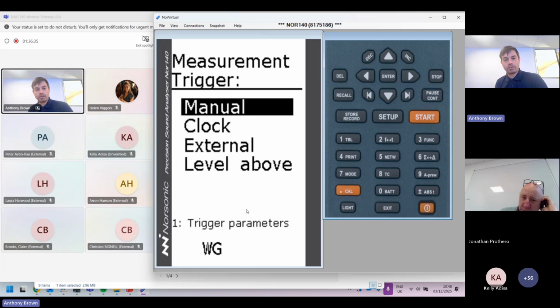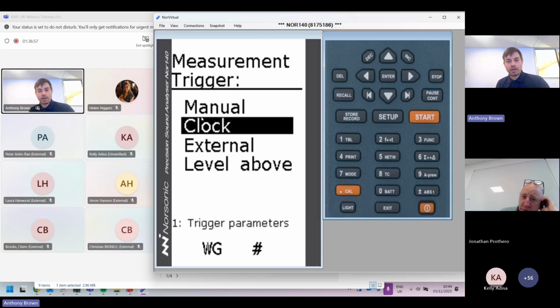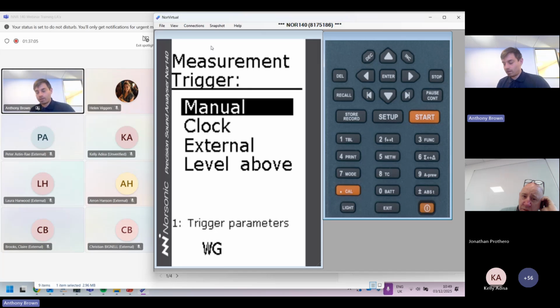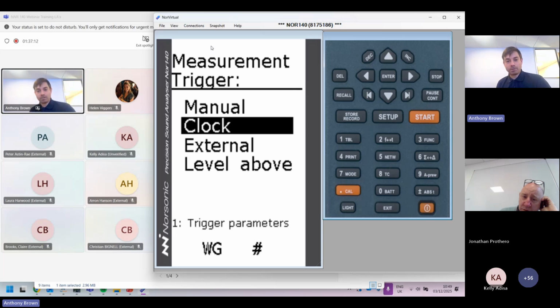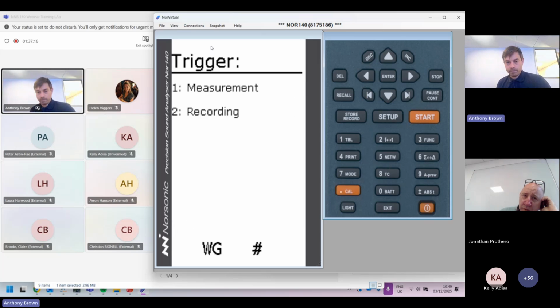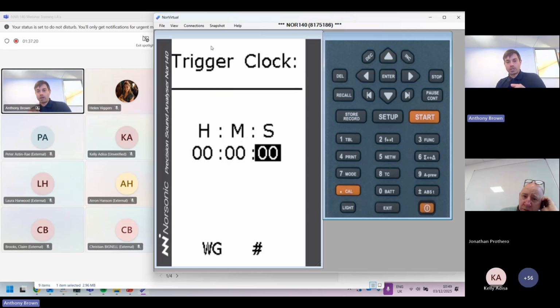So in number 1, measurement, if you go into that, you need to make sure, this is the critical part, that your cursor is set on manual. For the person whose meter was showing the W when they pressed start, it was because someone had set it to clock. What that means is these options control how the start button works. The start should work manually, but if you set it to clock, when you press the start button, it will wait until a certain time to start measuring. In this case, it means it will wait until 12 o'clock at night to start recording.